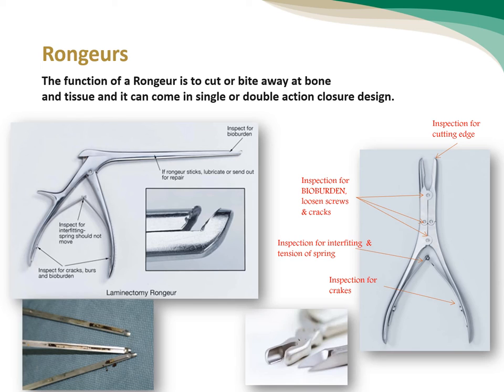We have to report it to the OR. If we have a replacement, we have to replace it. Also, on the bottom of the slide, we have the laminectomy. Inside, there is a remaining of tissue and blood after sterilization. We say it can be after sterilization because it's blackish already. We have to check it carefully, even if we have to force it open, and clean the instrument well and return it again. That's the slide about the rongeurs. Okay.